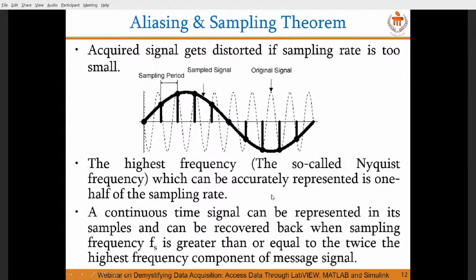So this is very important. The point is, you have to know the frequency of your input signal to select a proper data acquisition card, even if you're buying a ready-made one. You have very little choice in that case, because standard DACs come with their own preset sampling time or samples. So you go with a data acquisition board that is close to your requirement. You have to understand the frequency of variation of your signal and the sampling frequency of your data acquisition system.